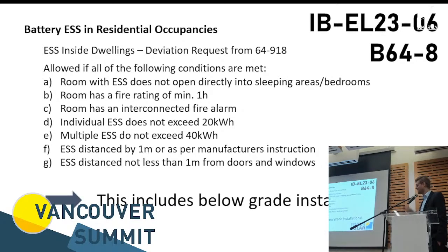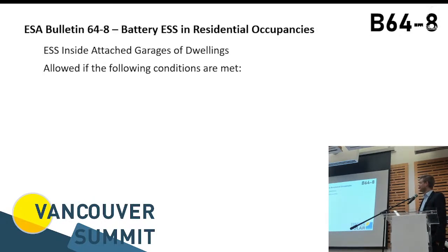And if you have all of that, then you can even install it in a dwelling or even below grade, which is actually quite decent, because now we have a way where, even though the code is written very poorly, there's still an avenue to sell systems to customers, actually install them, and pass inspection. It gets easier if you put it in a detached or attached garage. The funny thing is, most building codes, when they talk about a detached garage, it doesn't need to be fully detached. It can be a garage within the house. But from a fire safety perspective, the rating, it's still considered detached.